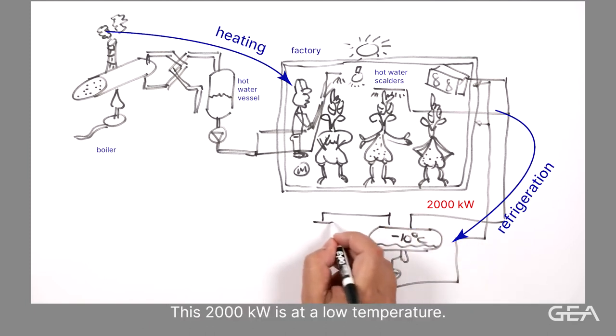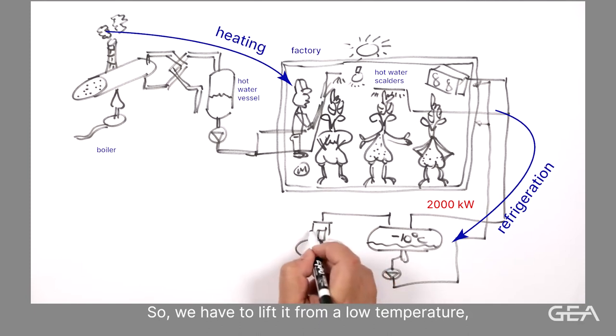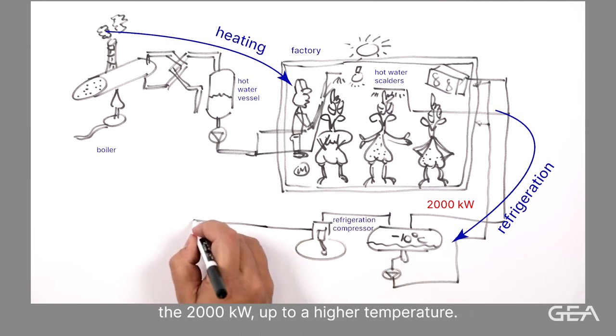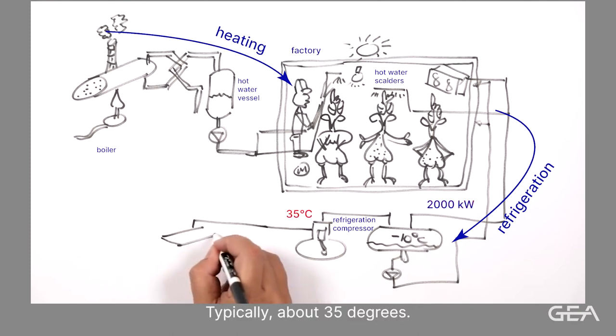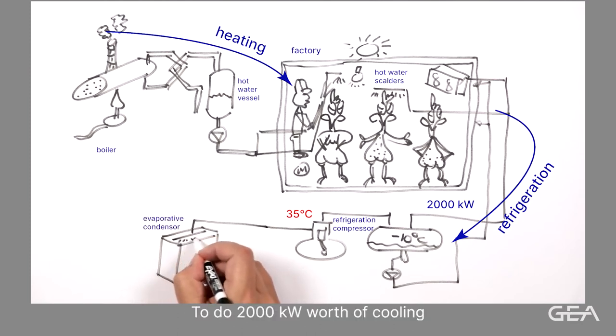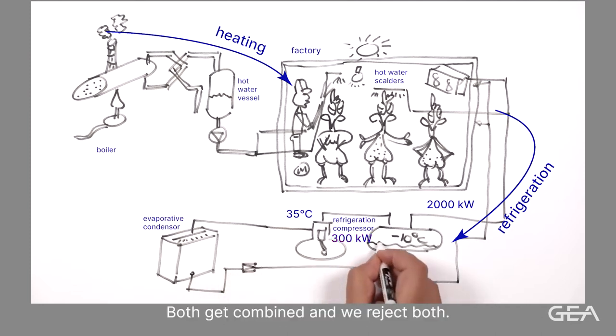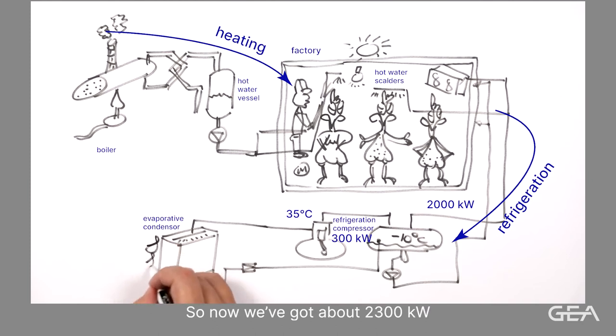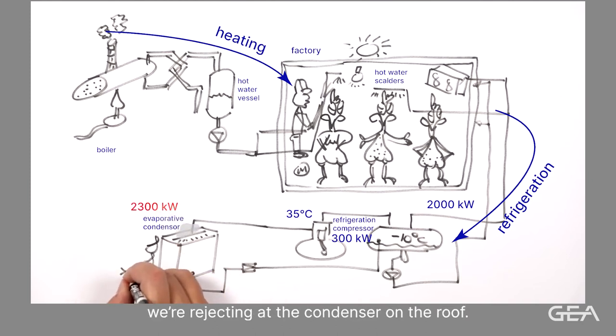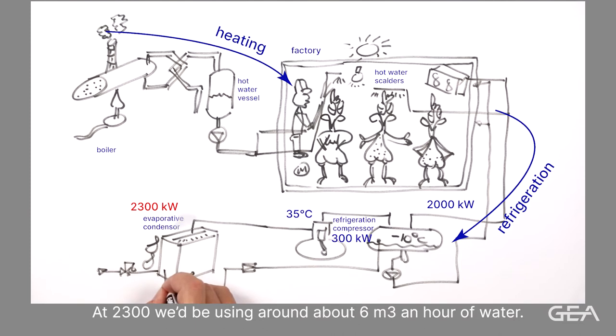This 2,000 kilowatts is at a low temperature. So the refrigeration process means we have to reject it to the outside air. So we have to lift it from a low temperature, the 2,000 kilowatts, up to a higher temperature, typically about 35 degrees. But it takes energy to do that via your refrigeration compressor. So to do 2,000 kilowatts worth of cooling, we have to put in another 300 kilowatts worth of electrical power in the refrigeration compressor. Both get combined and we reject both. So now we've got about 2,300 kilowatts we're rejecting at the condenser on the roof. And to reject that amount of heat we have to evaporate water. And at 2,300 we'd be using around about 6 cubic metres an hour of water.